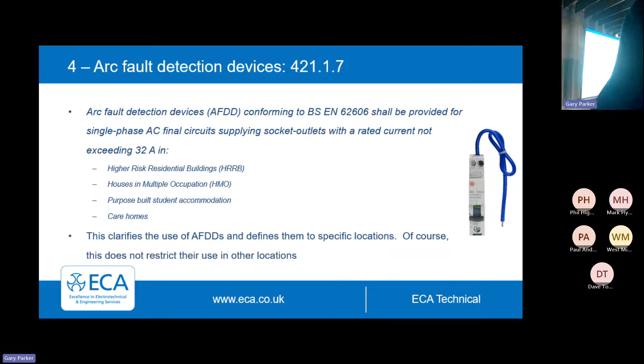They are useful, but limited. And like I said, they're not useful on lighting circuits, for instance, because there just simply isn't a load. So you could spec them, they just wouldn't do anything. You could spec them for socket outlets, but it would only be a limited area of protection, not the cable, but whatever's plugged in. So they can be used, and shall be used, in those cases, but the benefits are restricted. So does that answer your question? Brilliant, no worries.